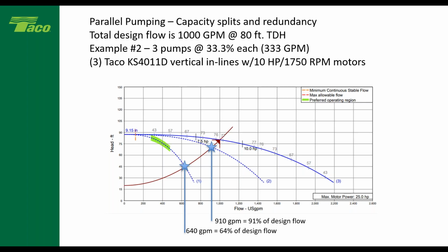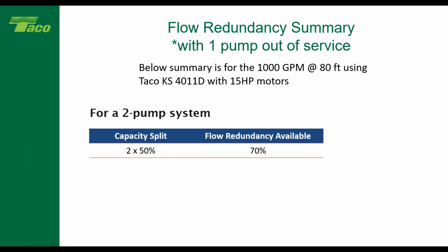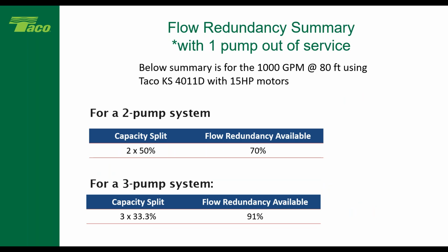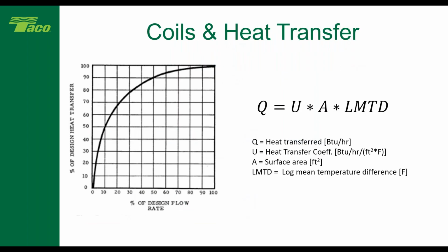Okay, now I know everybody's saying, well, that's still not 100% of the design flow. So if I look at this in summary, 2 at 50% gives me 70% redundancy, 3 at 33% gets me 91%. This is why this is important. We all know the heat transfer formula, that BTUs equals U times A times LMTD, where U is the heat transfer coefficient of your coil, A is your surface area of the coil, and then LMTD, of course, is the log mean temperature difference. This chart is straight out of the ASHRAE handbook. I didn't make this up, I promise.